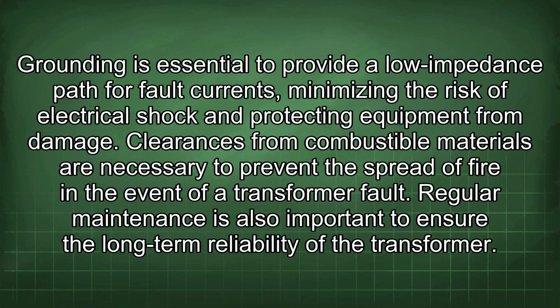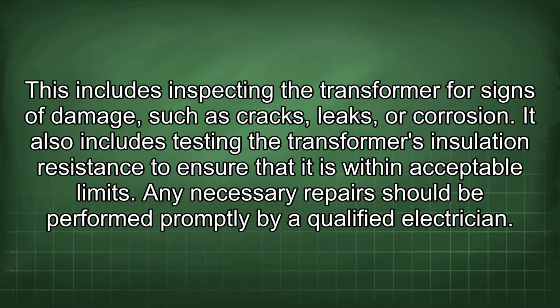Regular maintenance is also important to ensure the long-term reliability of the transformer. This includes inspecting the transformer for signs of damage, such as cracks, leaks, or corrosion. It also includes testing the transformer's insulation resistance to ensure that it is within acceptable limits. Any necessary repair should be performed promptly by a qualified electrician.